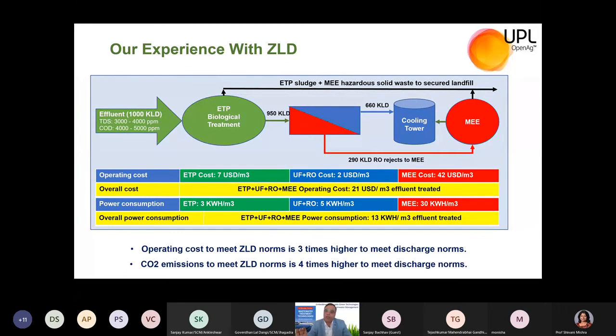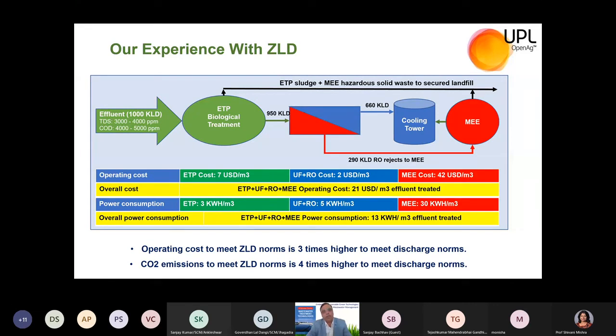The reject which goes to the multi-effect evaporator (MEE) costs nearly $42 USD per cubic meter. So when you combine all the techniques and divide by the inlet effluent per cubic meter, the combined treatment cost comes to nearly $20 to $21 USD per cubic meter when ZLD is achieved.